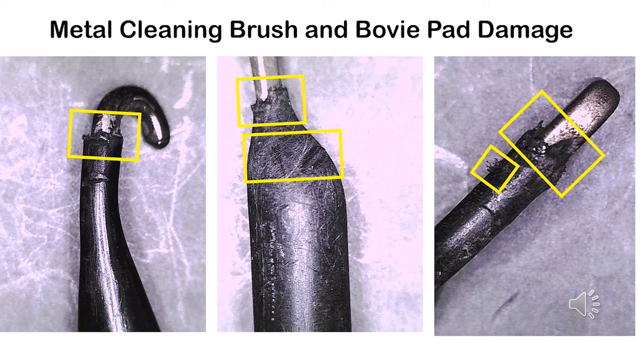In the middle, this is a combination of using a Bovie pad from the OR and a metal brush. And again, this is not correct, and you can see that it's causing grooves and gouges within the insulation that now is going to be an area of concern of keeping back debris. The picture on the right, again, a prime example of using a metal brush where you can see the frayed insulation that could possibly go into a sterile cavity.